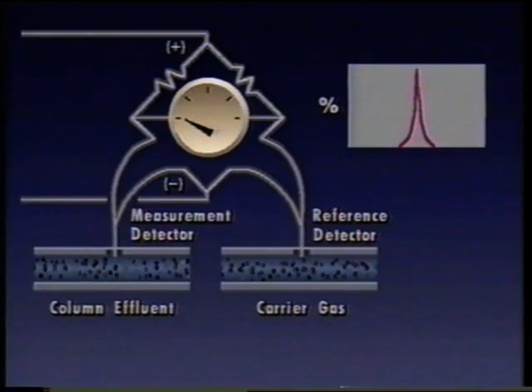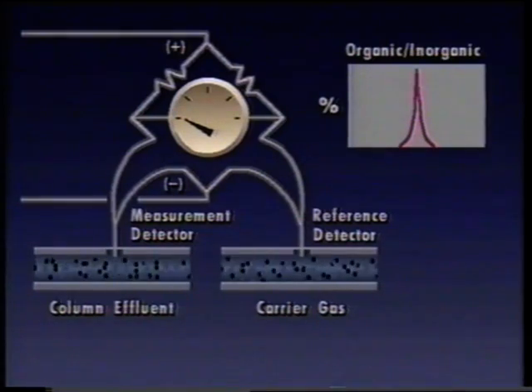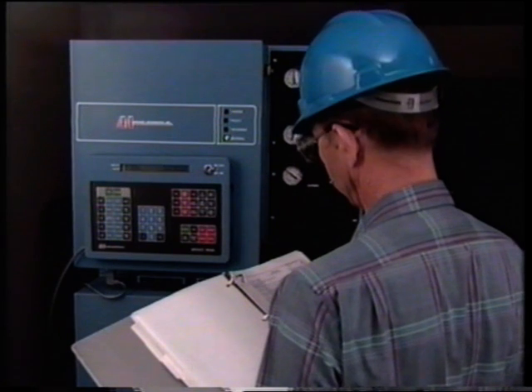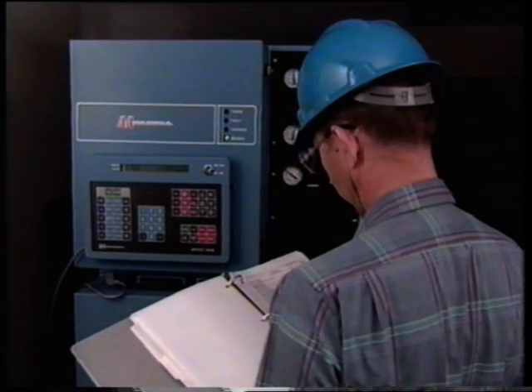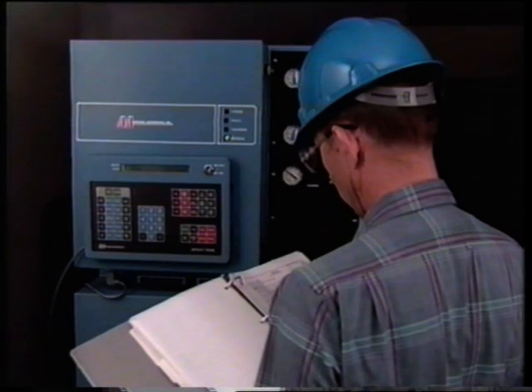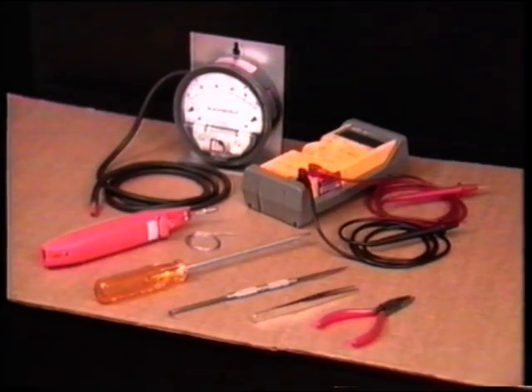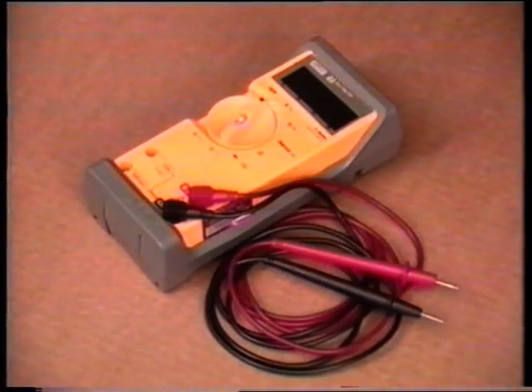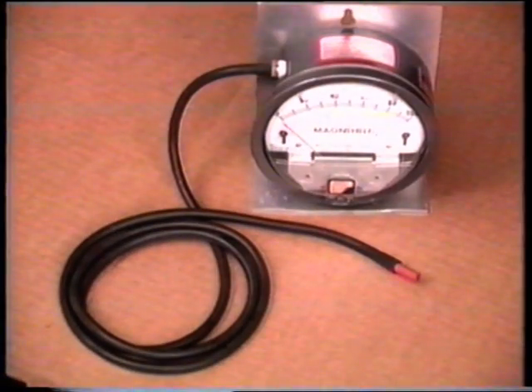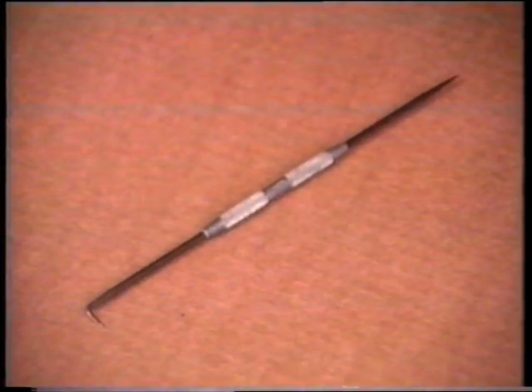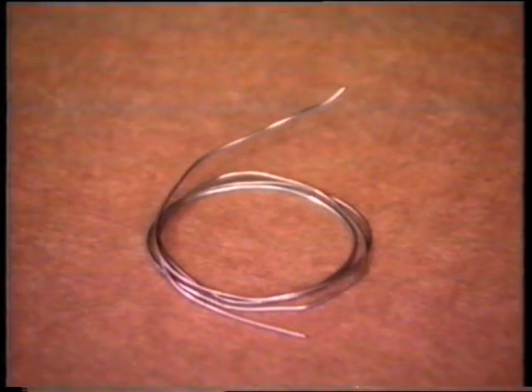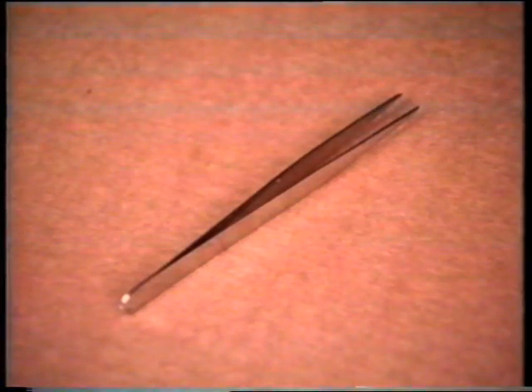This measurement is usually expressed in percent concentration. The thermal conductivity detector can be used with both organic and inorganic samples. Detector malfunctions may be traced to the detector assembly or the electronics section of which the detector is part. Some tools that may be needed for maintenance of the thermal conductivity detector assembly are a multimeter, small needle nose pliers, soldering iron, magnehelic flow meter, scribe tool, screwdriver, high temperature multi-core solder, and small tweezers.